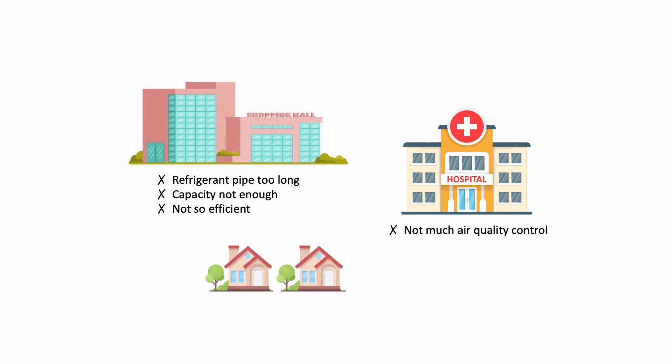The third one is why we're asking why VRF is not installed in residential houses. We have the small 4-ton unit, so good. Why are we not installing? Because it's just plain too expensive. Compared to multi-split and single-split, VRF system is very expensive. If you compare the price, you get a quote from manufacturer, it's very expensive. Not just the equipment itself is more expensive, but because you have the Y-joint, you need labor to weld it. If your labor cost in your area is expensive, then even more expensive. Even your labor cost is cheap, but you still need a lot of work. Because usually the single-split or multi-split, we just pull one stretch of refrigerant pipe, the copper pipe. We don't need to do any welding, except at the connection there. But now you have to weld all the Y-joints, three welding spots per Y-joint. There's a lot of work, so it's too expensive.